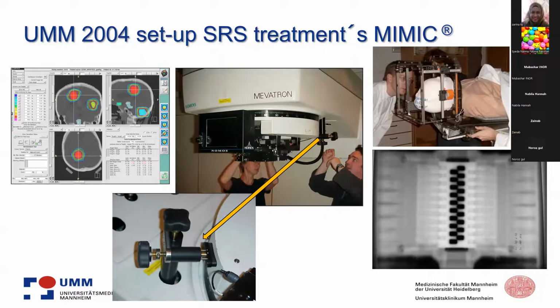Also, the QA plans in general were based on film dosimetry. So you see, we always identified issues where the MLC calibration was not sufficient for the IMRT. In that case, you had a long and intensive test and QA part before you could treat a patient, and also you have to intensify your QA of the machine calibration. You see this typical fence test. You see here the bed calibration as well. And of course, everybody who stepped into film dosimetry for the first time knows how long it takes to have a really good chain for film dosimetry available.